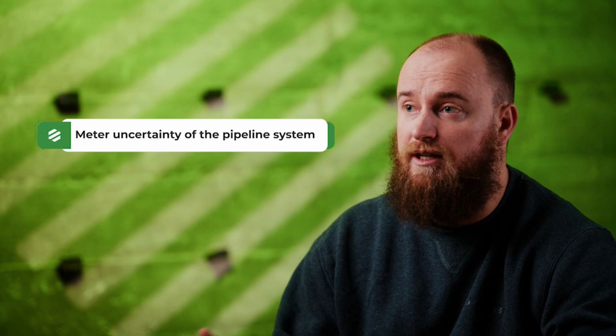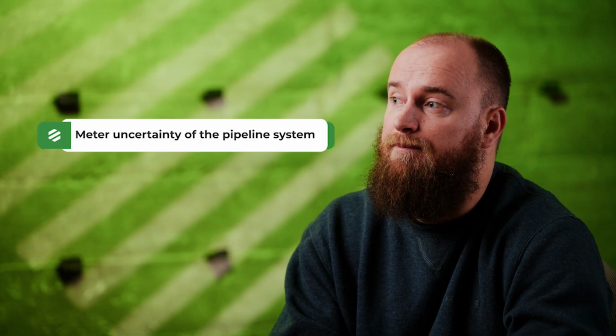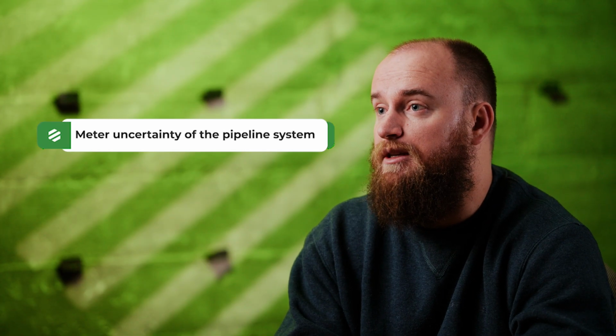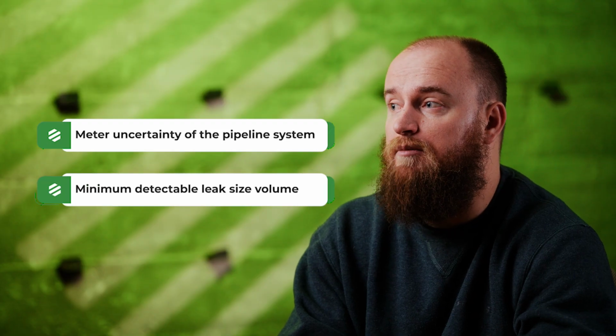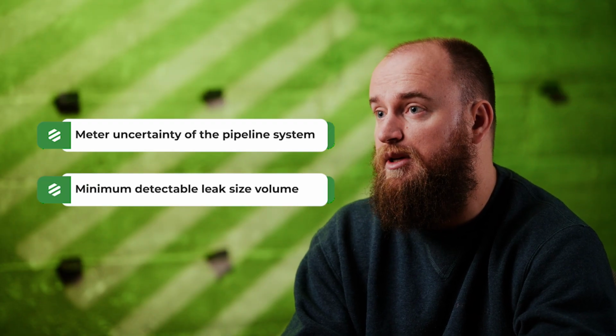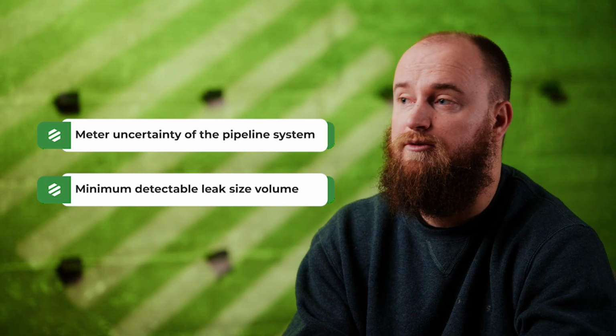Based on what the meter parameters or meter characteristics are, we can calculate the meter uncertainty of the pipeline system, and using that meter uncertainty we can determine what the minimum detectable leak size could be on that system, and that's what we target for our ultimate sensitivity of the leak detection system.